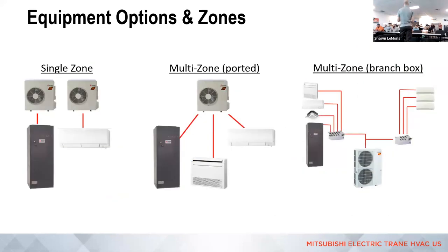Looking at ways to do heat pumps in the house: single zones, multi-zones, and bigger multi-zones. Branch box versus ported is really the key there. On your left you'll see a branch box hanging off that mobile display, with pipes coming out the back going to the different pieces of equipment. A ported version does almost the same thing, it just doesn't have that branch box in it. That has to do with some technical details, but it allows us to get to more zones throughout the house with one piece of outdoor equipment.